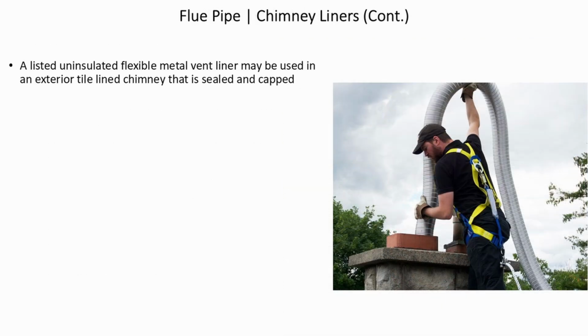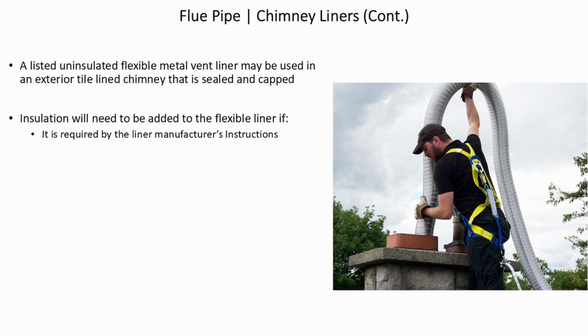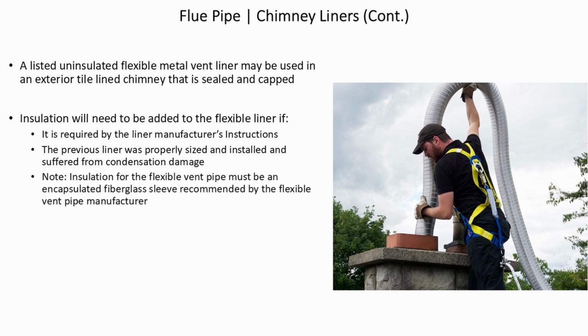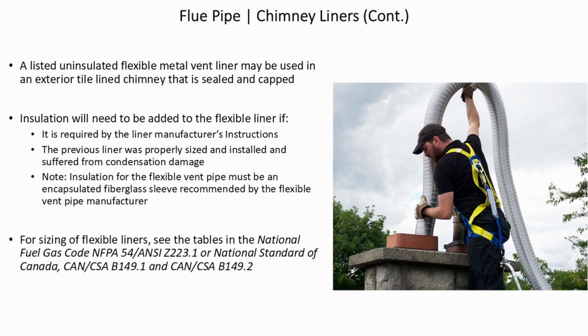A listed uninsulated flexible metal vent liner may be used in an exterior tile-lined chimney that is sealed and capped. Insulation will need to be added to the flexible liner if it is required by the liner manufacturer's instructions, or if the previous liner was properly sized and insulated and suffered from condensation damage. Insulation for the flexible vent liner must be an encapsulated fiberglass sleeve recommended by the flexible vent pipe manufacturer. For sizing of flexible vent liners, see the table in the National Fuel Gas Code, NFPA 54, ANSI Z223.1.